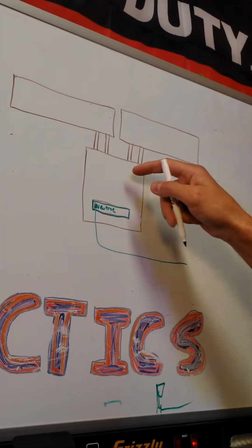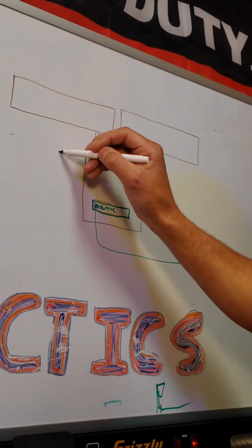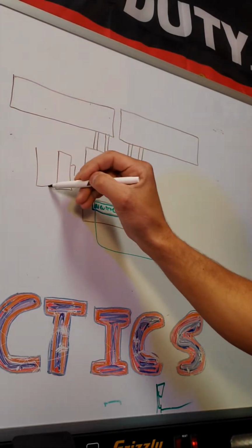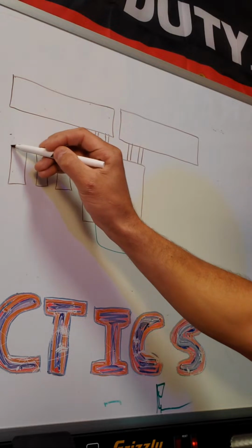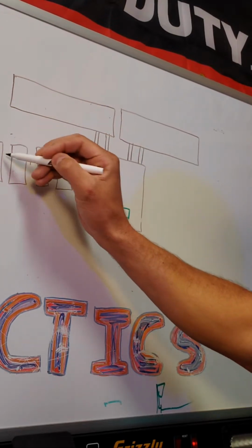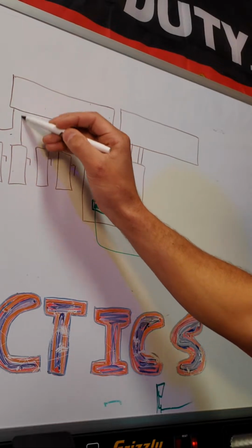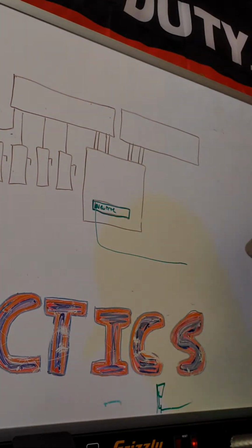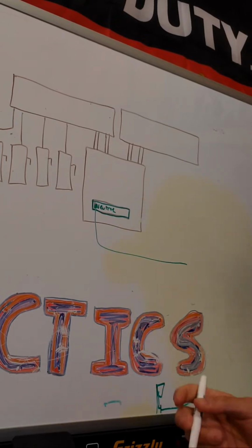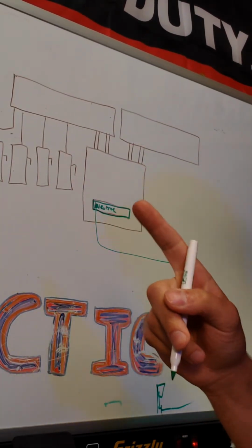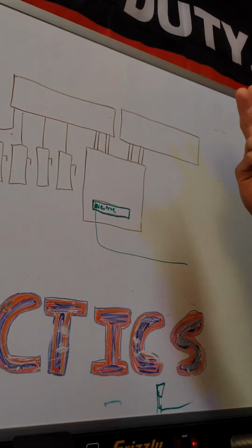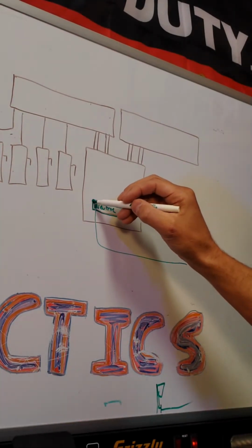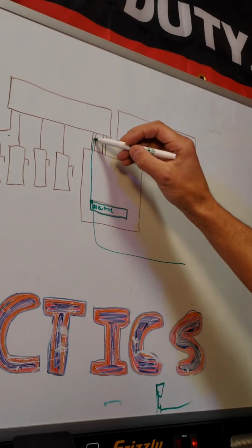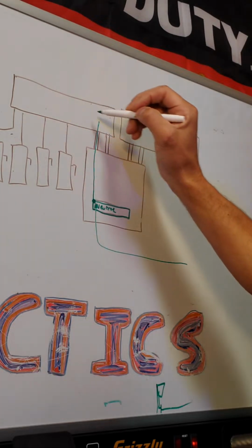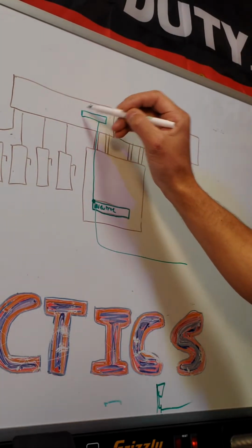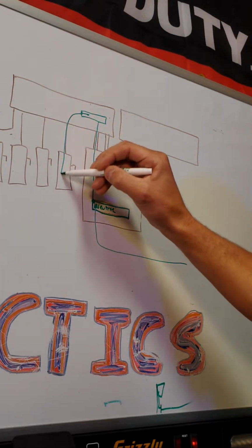And then out of here, out of this tap can, they had 4 different disconnects here. 1, 2, 3, 4 different disconnects, okay? What we know is we only need one number 4 for our grounding. So they did that. They ran one number 4 from this point up here, and they hit a ground bar. And then they ran an individual number 4 to each disconnect.